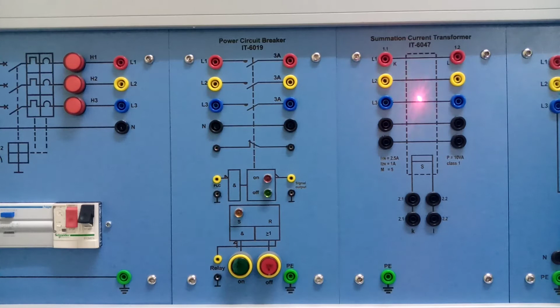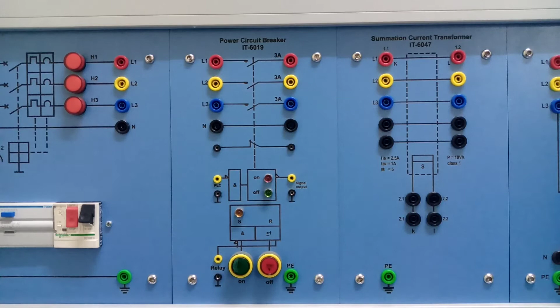Next up, we have a summation current transformer. We have used it in previous labs as well. For the summation current transformer, again red, yellow, blue. Now these are combined, and also the neutral connection. Combined, you can see that this is the primary, the red, yellow, blue. This is the primary, okay. And then here the next connection, and then these are the secondaries, okay. These are the secondary of your transformer. So the summation is given here, okay. So this is your summation current transformer.